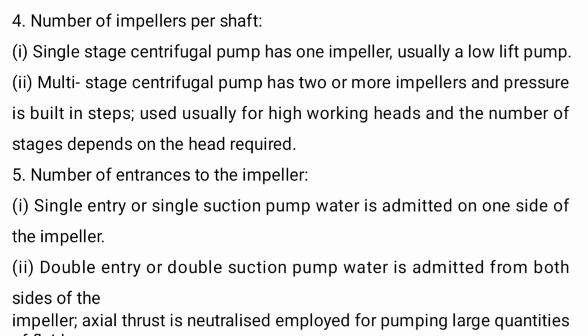The number of impellers per shaft. The single stage centrifugal pump has one impeller, usually a low lift pump. A multi-stage centrifugal pump has two or more impellers, and pressure is built up in steps, used usually for high working heads, and the number of stages depends on the head required.